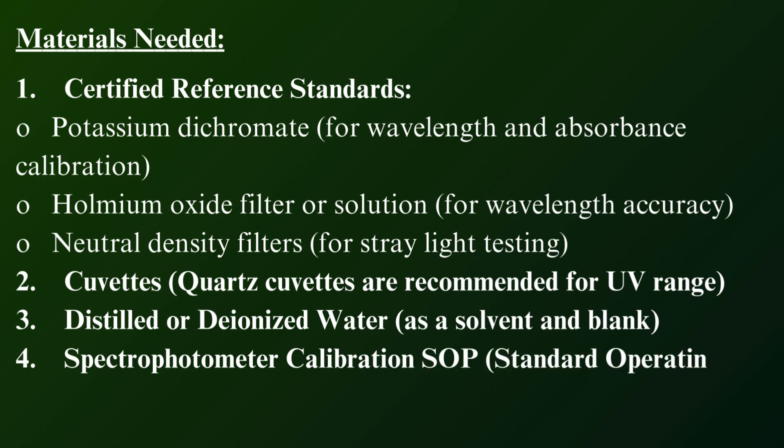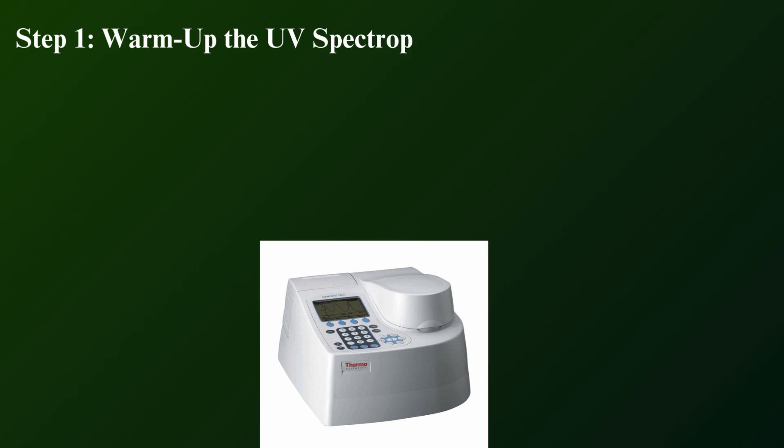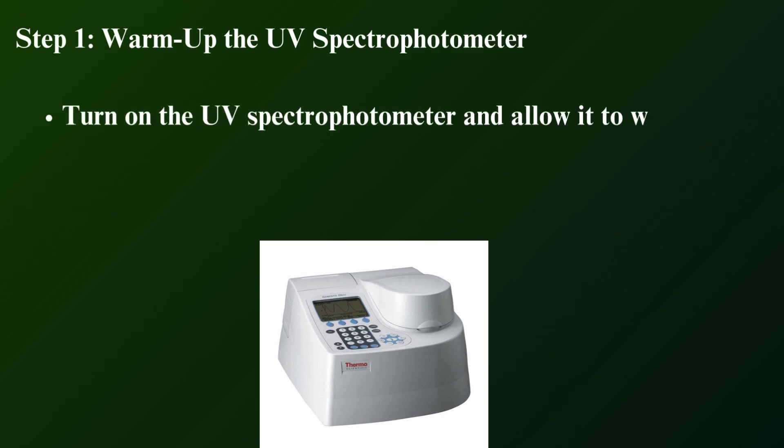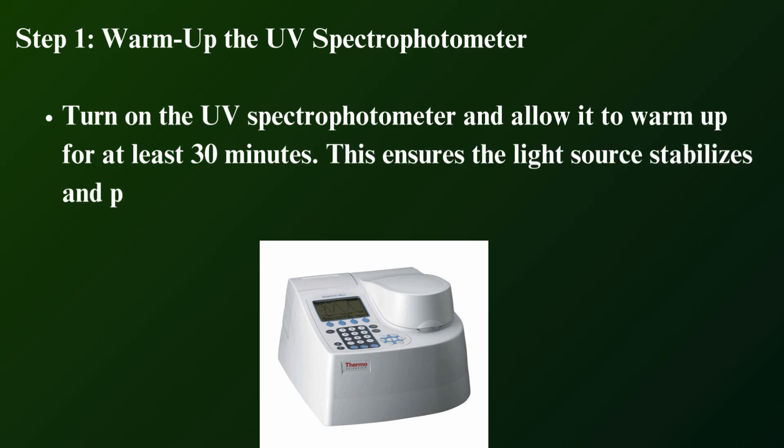Spectrophotometer calibration SOP (standard operating procedure). Step 1: Warm up the UV spectrophotometer. Turn on the UV spectrophotometer and allow it to warm up for at least 30 minutes. This ensures the light source stabilizes and provides accurate results.